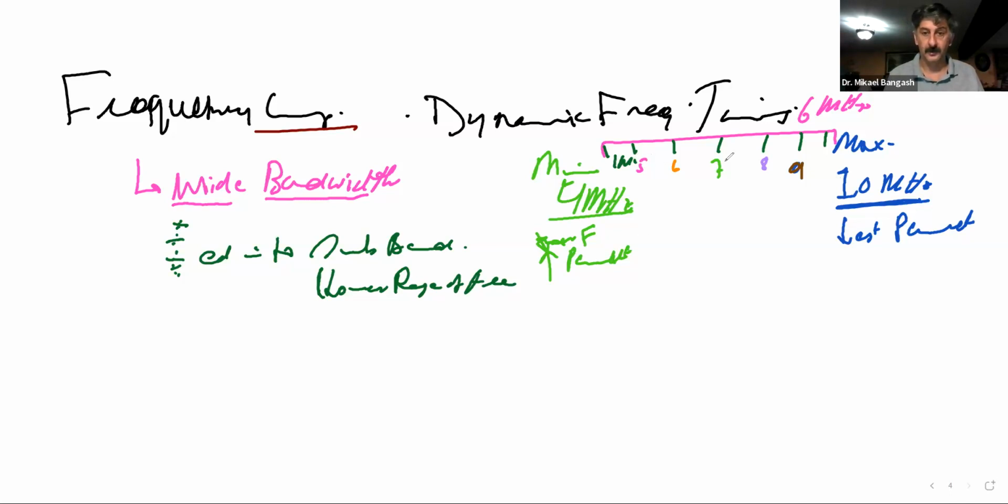We come across different subbands, where 9 is a frequency which is less than 10, which means that we will penetrate to a deeper depth than that of 10. 8 megahertz will be a lesser frequency than 9, so we have to penetrate deeper. 7 will be a frequency less than 8, and so on. So we actually have more and more penetration.